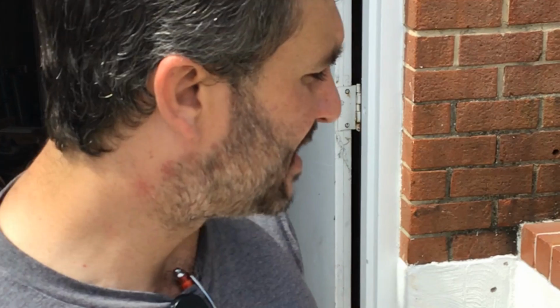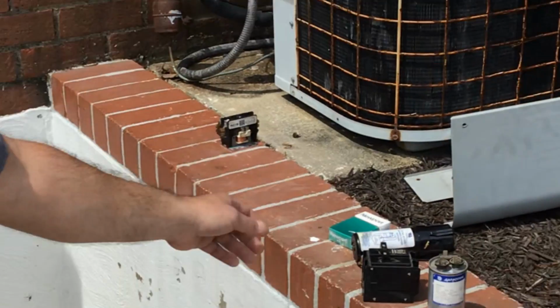Just check continuity on each side. If you don't have continuity through it, the fuse is bad. That's another reason you wouldn't get voltage to your outdoor unit. And then last is your circuit breaker.